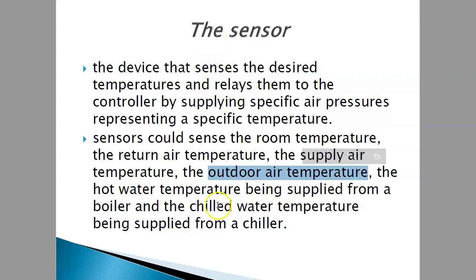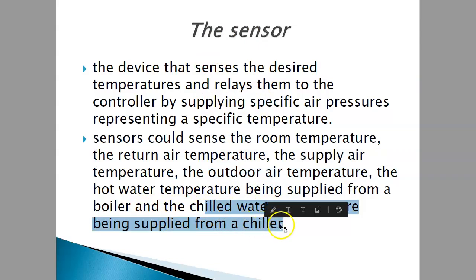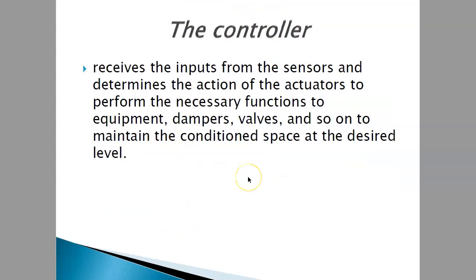Sensor could sense room temperature, the return air temperature, the supply air temperature, and outdoor air temperature. Whatever sensor, this is a temperature sensor actually. Hot water being supplied from the boiler, the chilled water temperature being supplied from the chiller. Whatever temperature is being sensed will be sensed by the sensor, specifically a temperature sensor. Okay, next one is the controller. The controller is to receive the input from the sensor and determine the action of the actuator to perform the necessary function to equipment, damper, valve, and so on to maintain the desired condition.